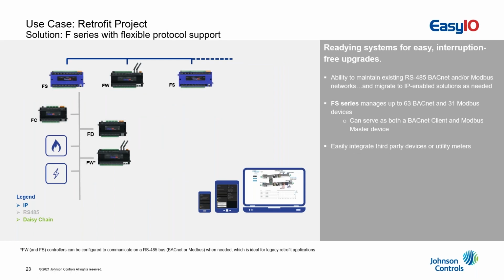Also for the brownfield, for the retrofit industry, if you have a building with an existing MS/TP network, RS485 network, you can also use it. It goes back to the beginning of my presentation, where I told you, you can use the IP connectivity of our controllers, but you can also use the MS/TP or the RS485 connectivity of our controllers. Like in this case, the FS RS485 port is being used as a BACnet or Modbus port to all the other controllers, but also to read third-party controllers or meterings or whatsoever. And at the same time, you can also make your building future-proof by adding the newest technologies on IP or features into the building.